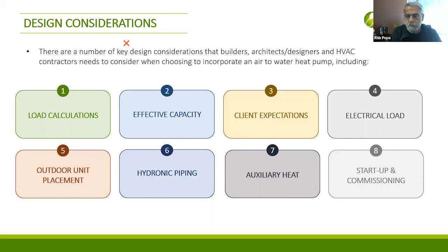So here's a little thing that I see all the time. Somebody's told, I need a 48,000, my heat loss is 48,000 BTUs. That's 4 tons, 12,000 BTUs per ton. And so you say, okay, well, I've got a 4-ton heat pump, perfect. That's not how it works. That heat pump's nominal capacity is measured at a certain temperature. They're all measured at that same temperature, which is 47 degrees Fahrenheit. And the capacity and efficiency of those heat pumps changes as soon as that temperature changes. So as you go down in temperature to your winter design conditions, in a lot of cases, so does the capacity and efficiency of that heat pump. So careful. You have to do your load calculations and measure the effective, not the nominal capacity of the equipment.